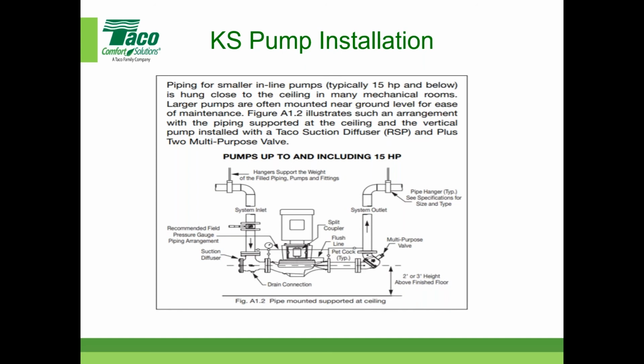For startup, we include, and it's right in our instruction manual for the pumps and the suction diffuser, a very finely meshed screen that needs to be removed prior to commissioning. It's there for startup because during the first couple of flows through the water, there may be some debris that needs to be taken out. Keep that in mind.